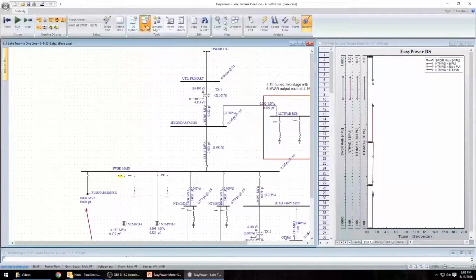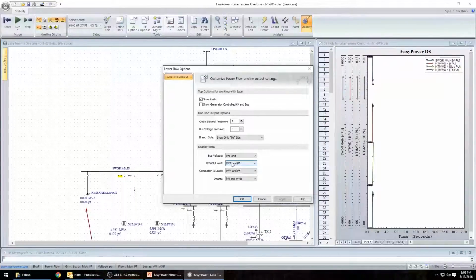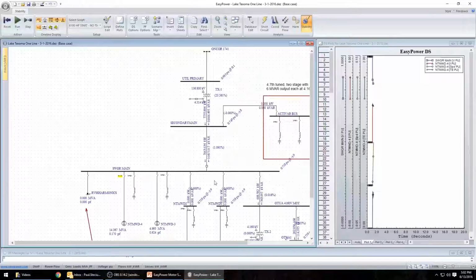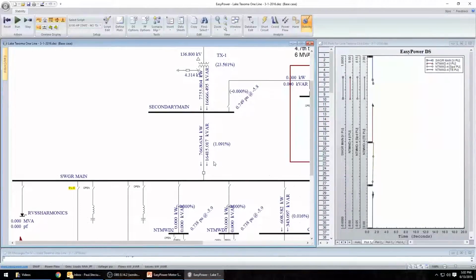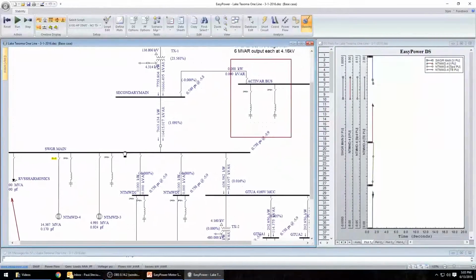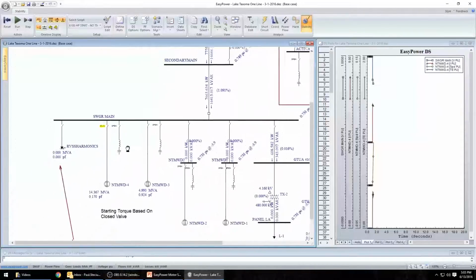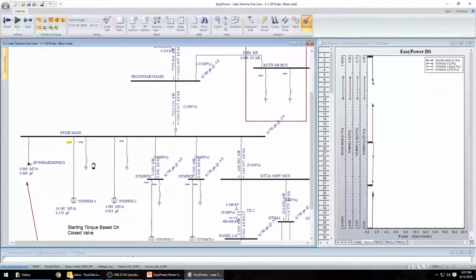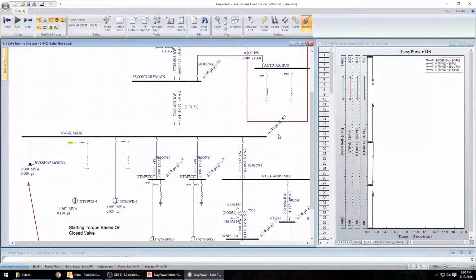You can go through and change the power flow options here and say, well, I want to look at kW and kVAR instead. And you can see that during starting of this motor, you get about 16.4 megavars, or 16,415 kVAR of flow, and that's resulting in this 0.73 voltage drop. And that's why this motor will not start. The voltage is simply too low to start this motor. That 0.73 per unit voltage represents about 49% of the torque to the motor, and with a relatively low starting torque to begin with, this motor fails to start.